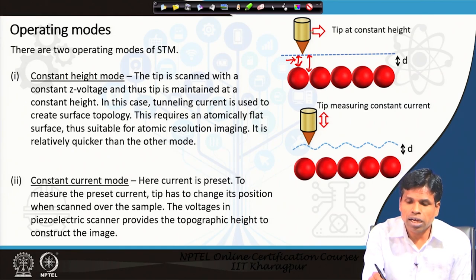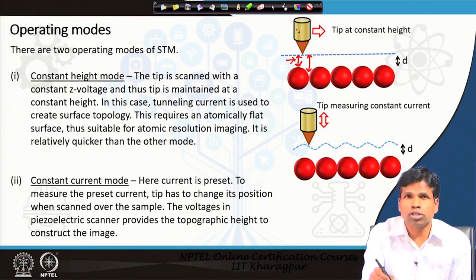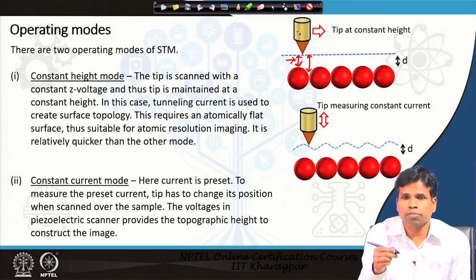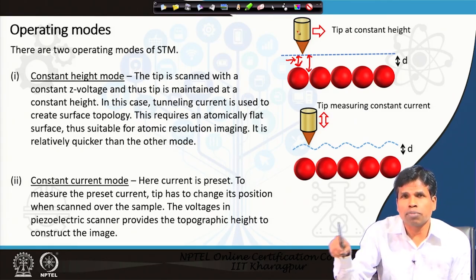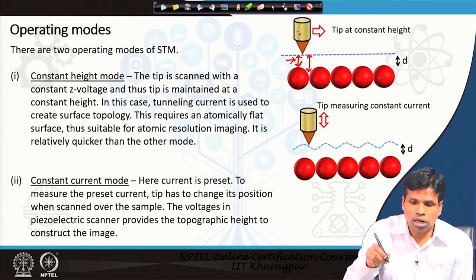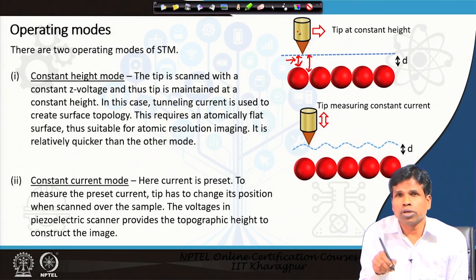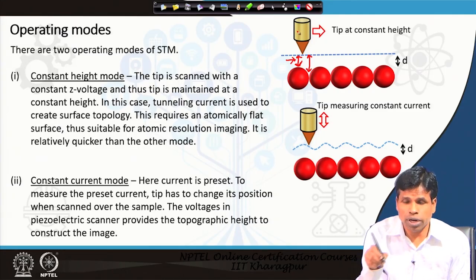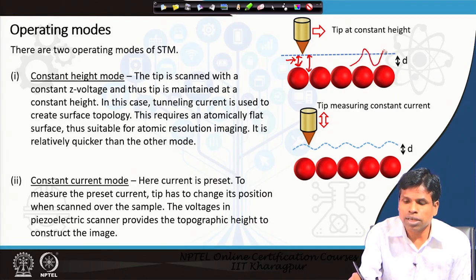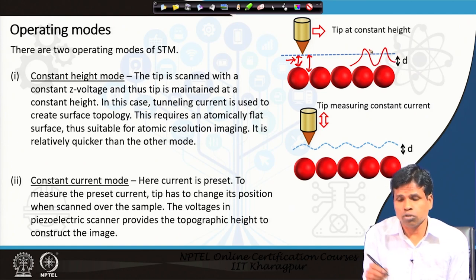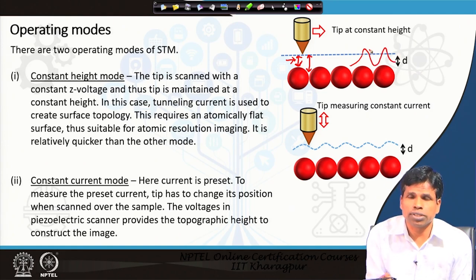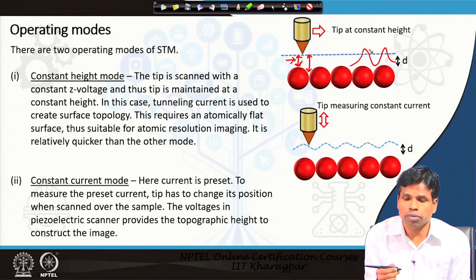Moreover, this is a faster way of scanning because we do not change the voltage to the piezo scanner, so the tip can move at a faster rate. The advantage is that we can scan very quickly. However, the disadvantage is that if the sample is very rough, the tip may crash. Once the tip crashes, artifacts will be generated, the tip shape will be distorted, and artifacts will form.